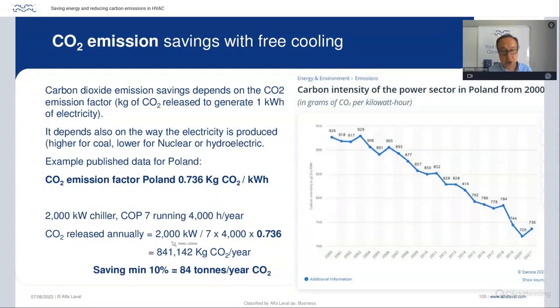And with this particular application, 2000 kilowatt cooling capacity, divide by the COP, times the hours running and the carbon emission factor. This chiller running 4,000 hours a year is releasing 841 tons of carbon per year, 841 tons. Now, if we can save 10%, it's 84 tons. And this is a major saving and a good sustainability focus. I don't know if we have consultants in this team, but our biggest challenge is to design more efficient buildings and to look at all the opportunities of saving energy and also have a green building with less carbon emissions, as we've shown here.